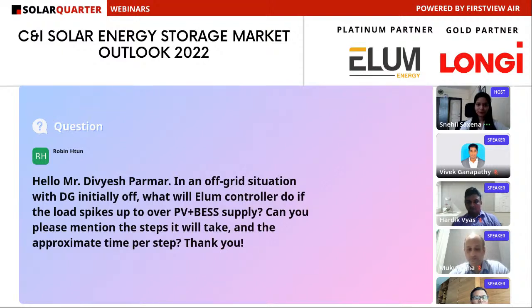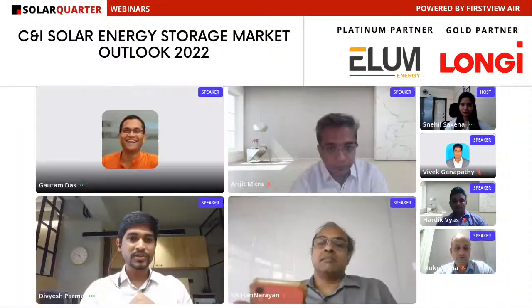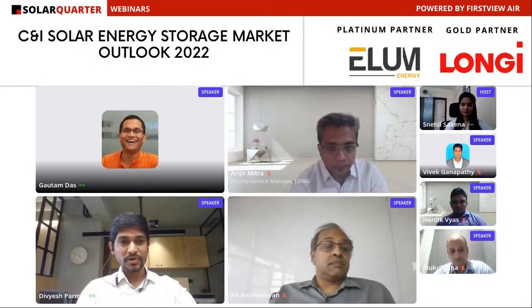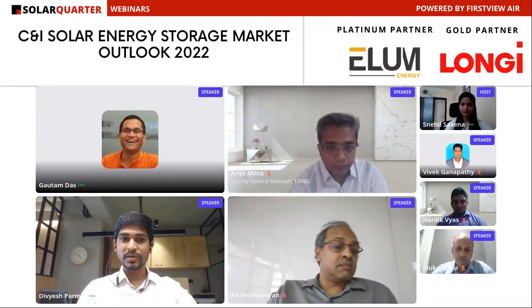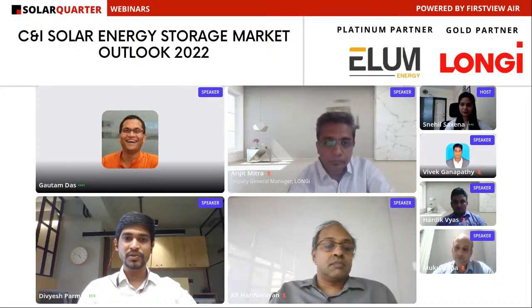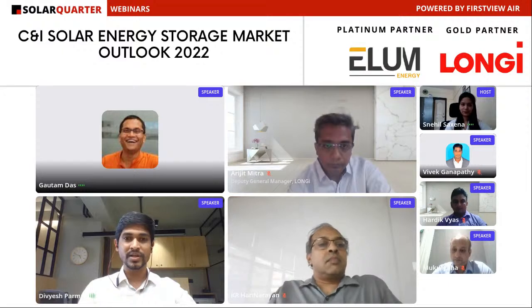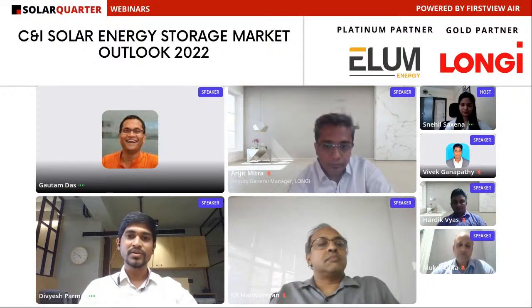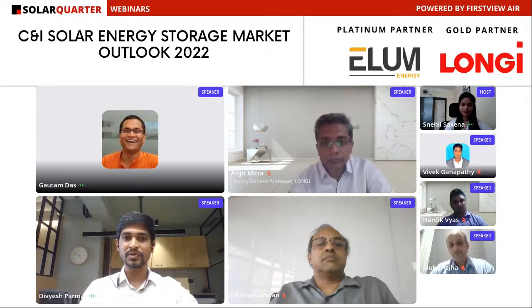To elaborate on the question about this function feature, it is covered under spinning reserve. For example, say your load is reaching 90 percentage of PV plus storage capacity. There is a function called spinning reserve, so when the load reaches 90 percentage, we will start the gensets in advance so that they are able to take the load when it goes above 90 or 100 percentage. By doing so, you save considerable time, like 15 to 20 seconds, which is required to start the gensets and be able to take the load. So the gensets start prior, and the increased load will be transferred to the DGs when the load is increasing beyond the PV plus battery capacity. Hope that answers your question.